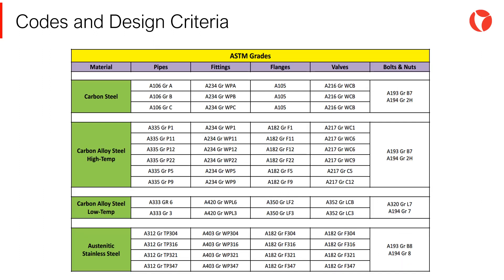The biggest challenge with the ASTM or ASME designation lies in the fact that even when the metallurgy is the same for the whole vessel — carbon steel, for example — components may have different designations depending on their fabrication method: cast, forged, welded, etc. For example, for carbon steel metallurgy, a pipe may be A106 grade B, while a flange would be A105.